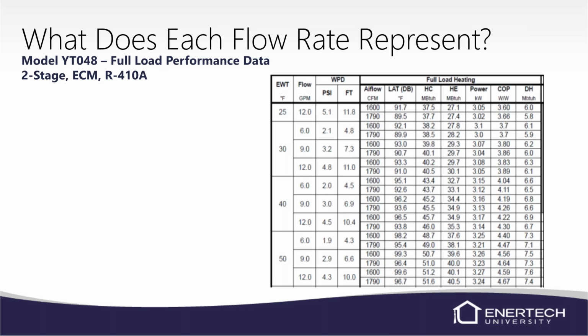Now, I told you we recommend on a closed loop 3 GPM per ton and 1.5 on an open loop. So these flow rates, that's the minimum flow rate for an open loop. So a 4-ton unit, 1.5 GPM per ton would be 6 GPM. So minimum flow rate for an open loop system is what we're showing there.